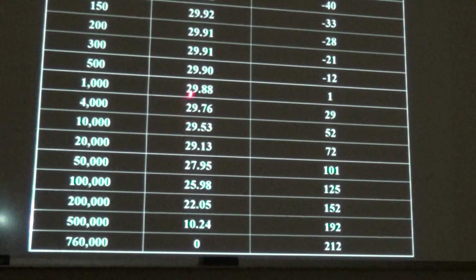As we go up, we're going to increase the vacuum. This is going to be at sea level. Everything from here is what they mean when they talk about a partial vacuum. So let's say that we get to the number that they recommend, 500 microns for the vacuum gauge, which is the equivalent of 29.90 inches of mercury. Water boils at -12 degrees Fahrenheit.